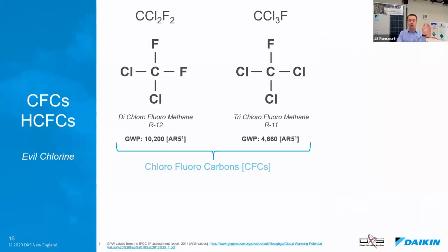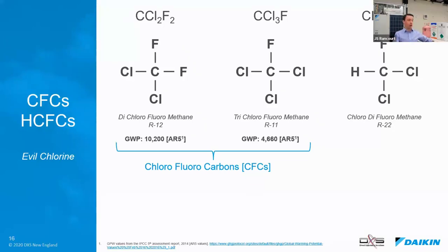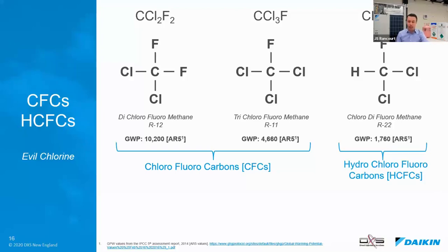These are chlorofluorocarbons. Sounds like a complicated name. It's usually one word. I just separated it out so we can read it better. They're called CFCs because they have chlorine, fluorine, and carbon as their components. That's it. Soon after R12 and R11 were invented came the first HCFC known as R22. I have a box sitting right here, 30 pounds of it right beside me. A much better GWP under 2000. This is a hydrochlorofluorocarbon. Why? It has a hydrogen, a chlorine, a fluorine, and a carbon. That's why they're called HCFCs.